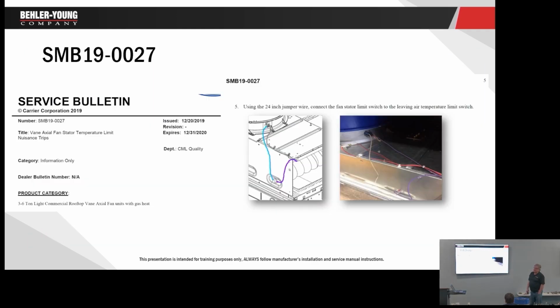Okay, there was a bulletin to replace that limit with an auto reset limit. Like I said, I didn't give you that bulletin now because if that unit's been running since 2020 with the manual reset, leave it alone and figure out why it's tripping. Okay, you're putting a Band-Aid on another problem if you try to change it to auto reset. So at this point, I wouldn't suggest that.